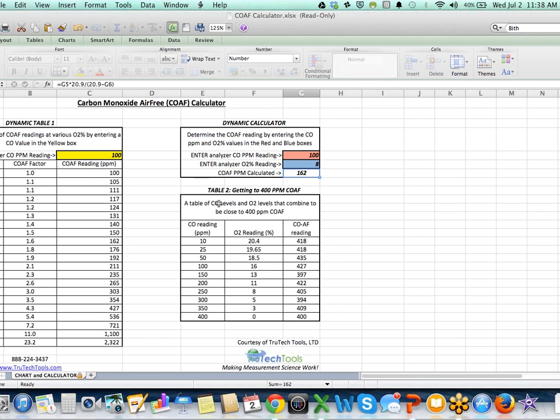And then this little static chart down here shows the standard we pretty much talk about, which is 400 parts per million CO air free for most appliances. So I did a little backwards calculation: to get into the range of around 400, what oxygen reading would you need, and what CO combination would lead you to that point? Of course, because it's two factors, it can be a blend of these different things. Anywhere from 0% oxygen and 400 parts per million leading to 400 CO air free, down to, and this is kind of ridiculous, 10 parts per million at 20% oxygen leading to 400. Typically more in the range of, say, 11 to 13, but at 150 parts per million and 13% oxygen, you'll be up there in that range of 400 parts per million.